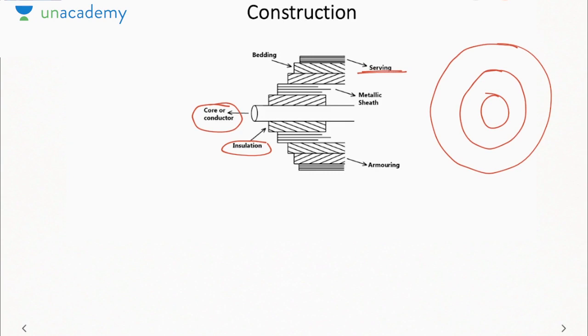Now, why are so many layers required? Because once the cable is laid underground, maintenance of the cable is difficult. So we need to protect the cable at any cost so that we do not have to clear a fault or replace the cable. That is why the installation cost of the cable is high, but the maintenance cost will be low. It involves only a one-time cost.